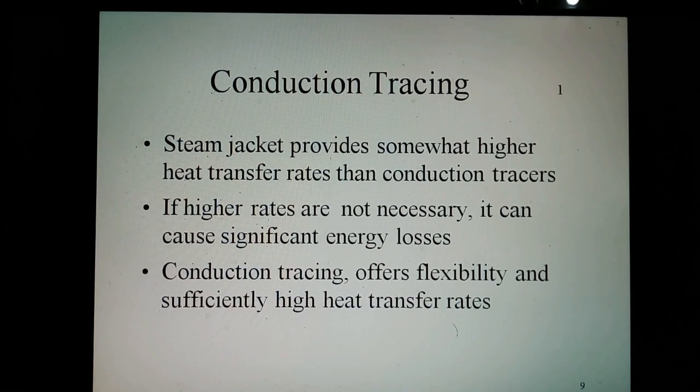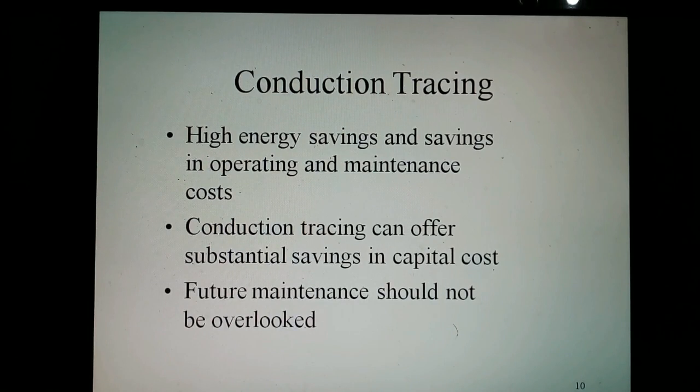The steam jacket provides somewhat higher heat transfer rates than conduction tracers. However, frequently these higher rates are unnecessary and can cause significant energy losses. Conduction tracing, with its flexibility and sufficiently high heat transfer rates, can reduce energy consumption by adjustment of the number and size of tracers to more closely match the actual heat requirements. Overall energy savings and reductions in operating and maintenance costs are of significant interest. Conduction tracing can offer substantial savings in capital outlay and heat maintenance which should not be overlooked.